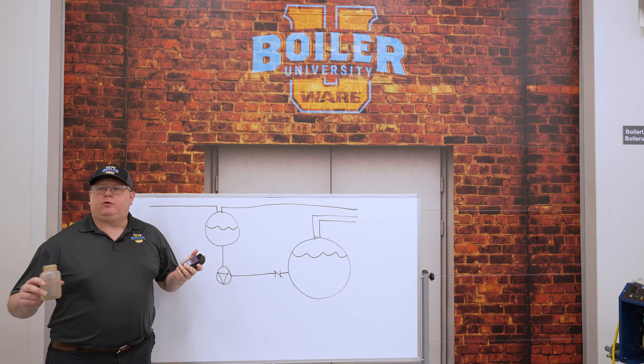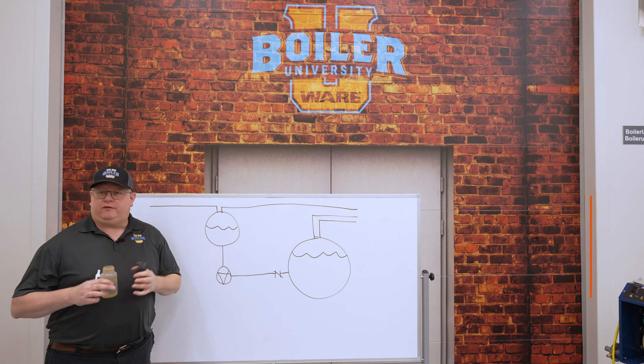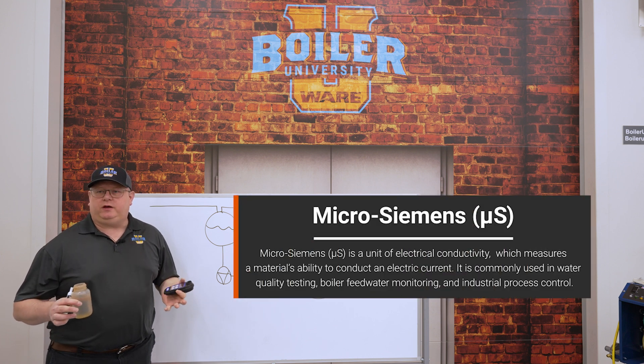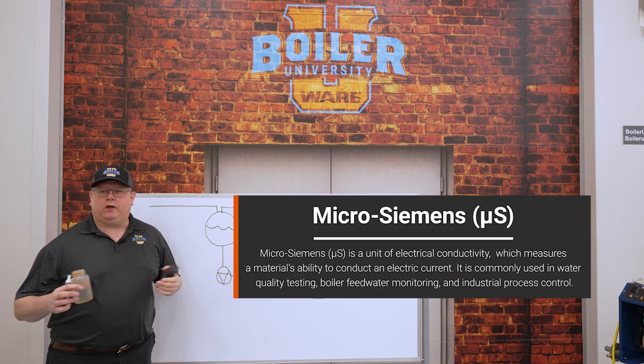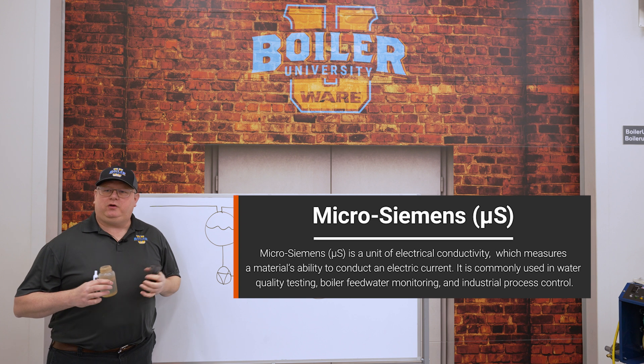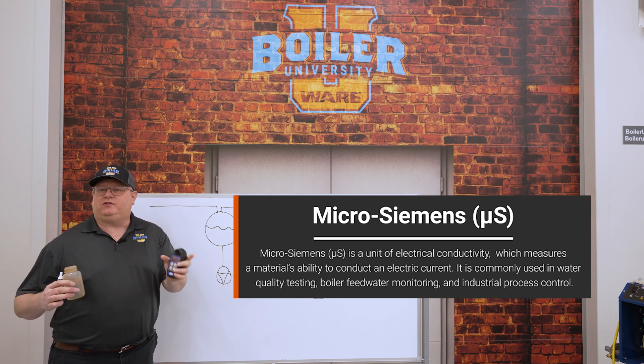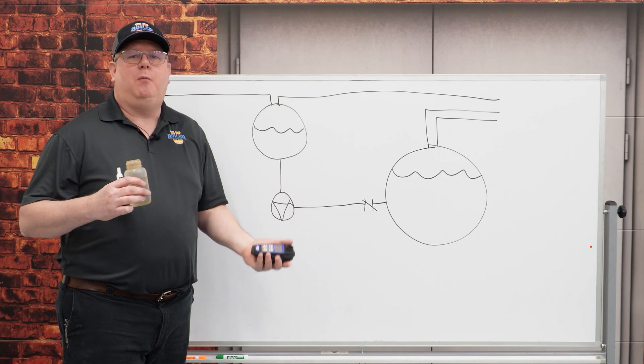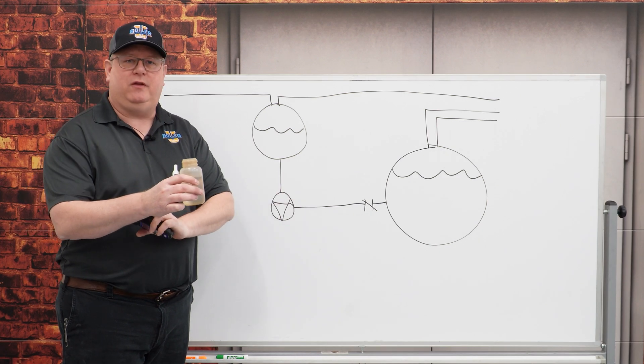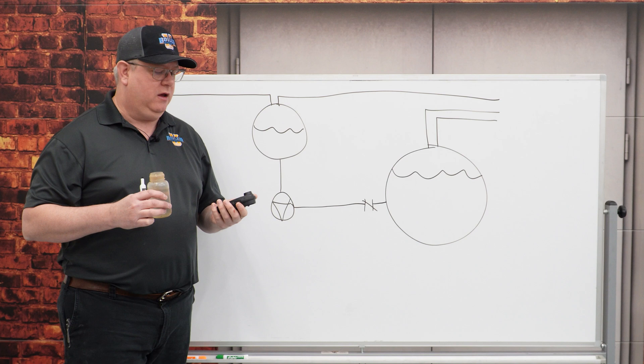If we're going to control conductivity on a boiler, the first thing we need to do is measure it, so we know the value of the conductivity in the boiler. The unit we often use for that is micro siemens. It's a conductivity unit, and basically the more dissolved solids we have in the boiler, the higher the conductivity will be.